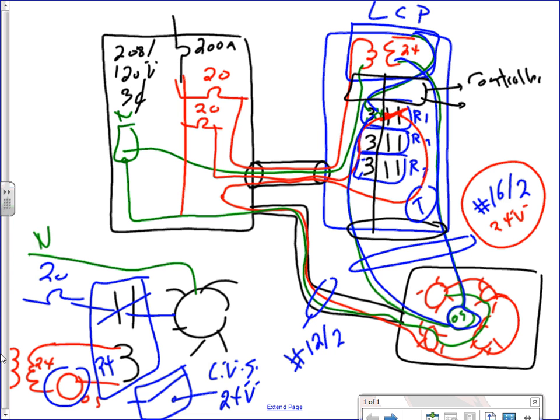Remember class-two circuits? This control circuit — the 16-2 low-voltage circuit — is a class-two circuit under NEC Article 725, which means you cannot put it in the same conduit as the line-voltage power circuit. They must be separated in terms of wiring.